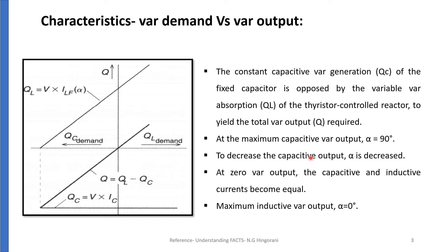At zero delay angle, i.e. alpha equal to zero, the thyristor controlled reactor conducts current over the full 180-degree interval, resulting in maximum inductive VAR output, equal to the difference between the VARs generated by the capacitor and those absorbed by the fully conducting reactor.